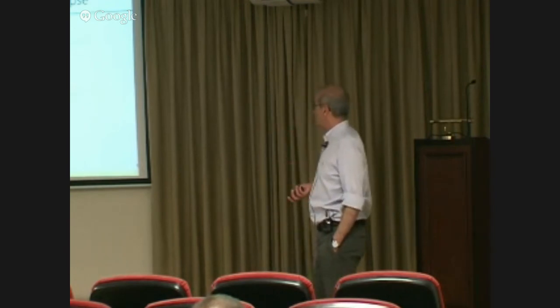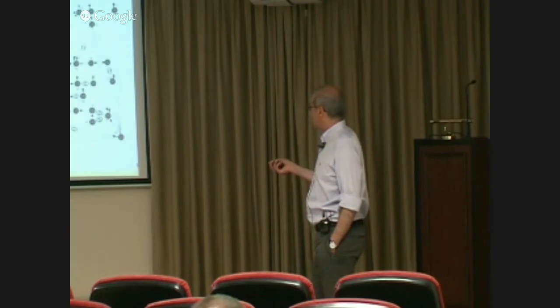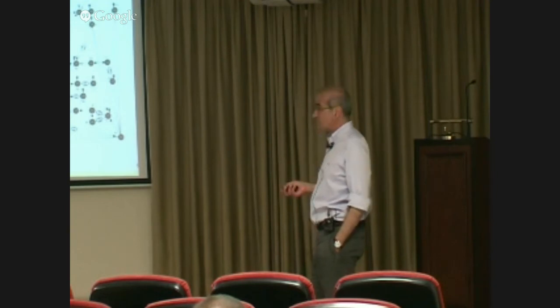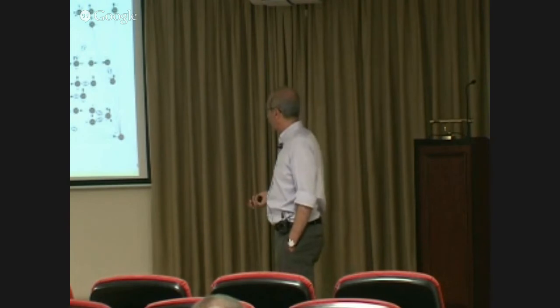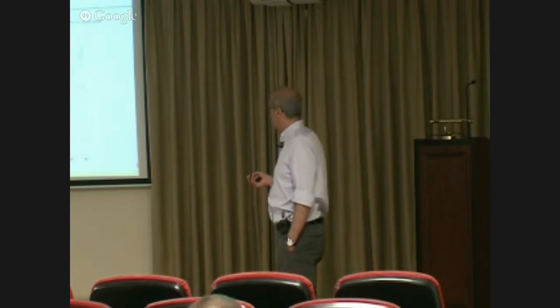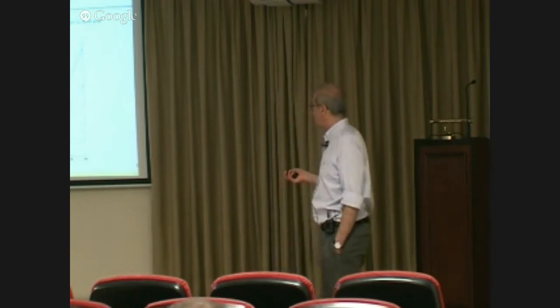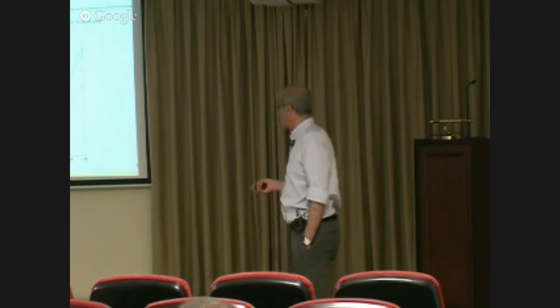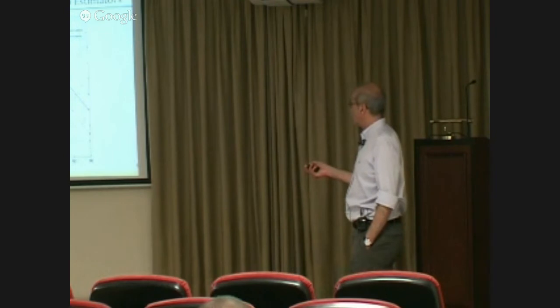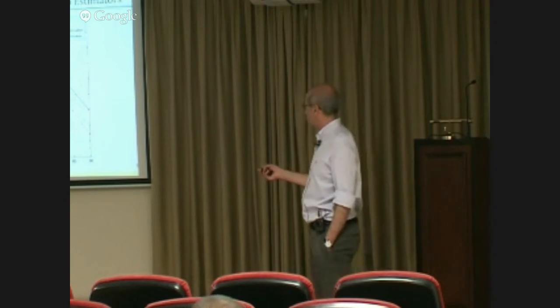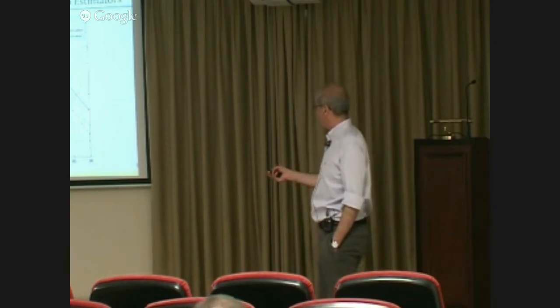So we tried both actually, and we created a collapse scenario like this. Here in this system, the voltage collapses here, and we don't have any PMU at this bus where the voltage collapses, but we have PMUs at buses nearby. And with that, if you compute the mean squared errors, or the deviations with respect to the true state, LAV performs slightly better than just using WLS. And also, if you look at the actual trajectory of this voltage drop, this is the true trajectory. Using LAV, which is shown in red, you do slightly better than if you used weighted least squares.